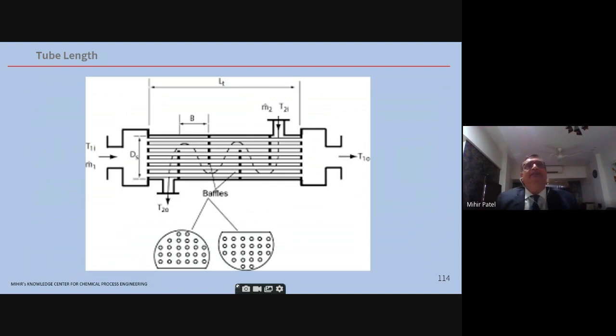There I have seen 50 mm tubes, but they are used specifically for cleaning services. So we'll go to the tube length. Now, as can be seen, tube length is shown as LT on the top. Okay. Baffle spacing is shown as B in the middle, if you see. And the baffle cut is shown. Okay. The horizontal baffle cut is shown here basically.